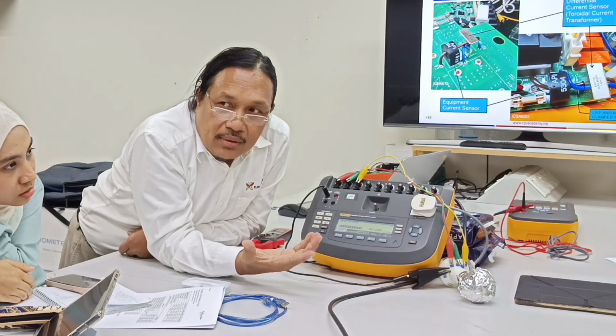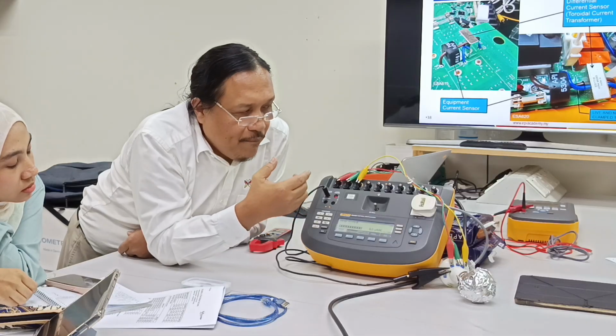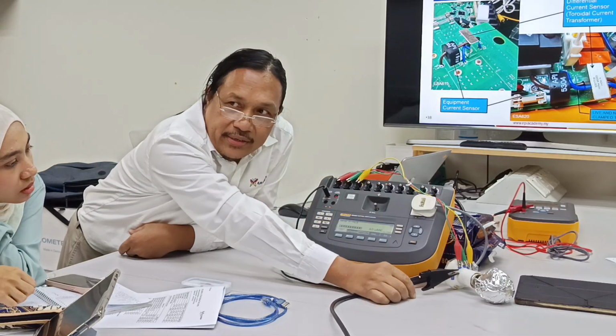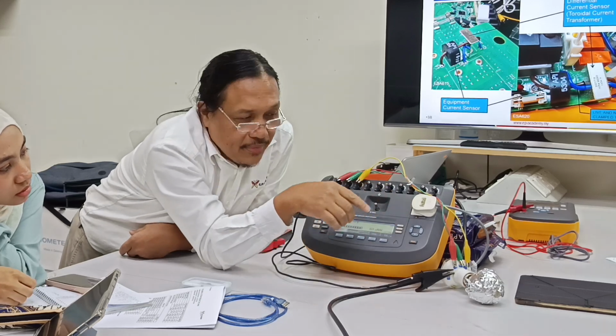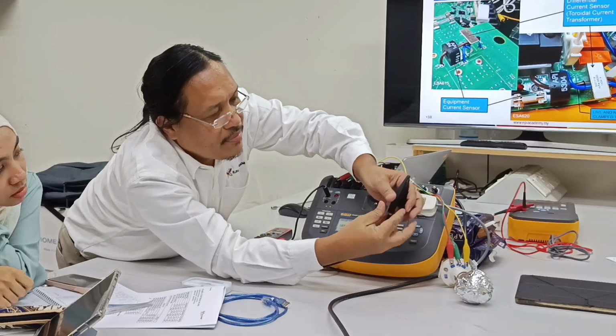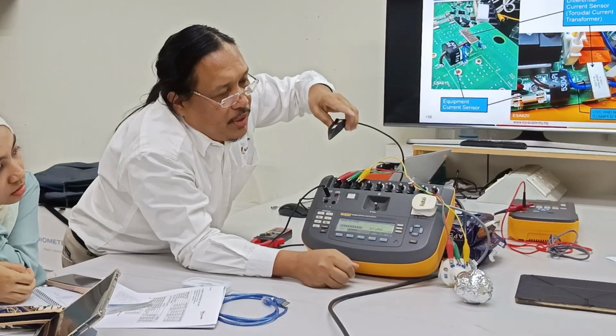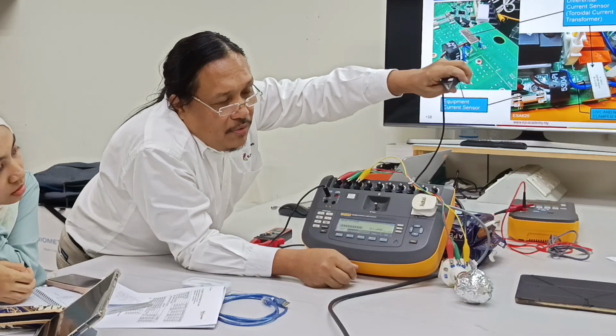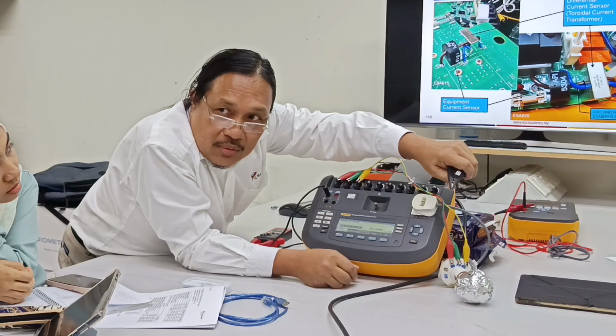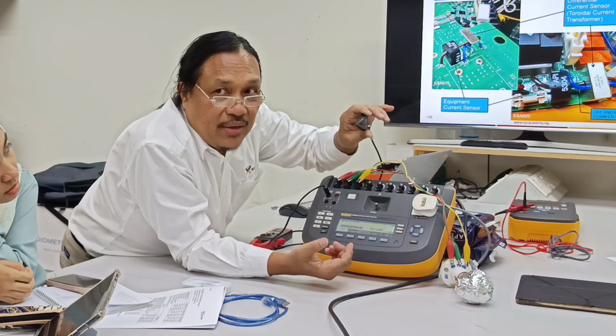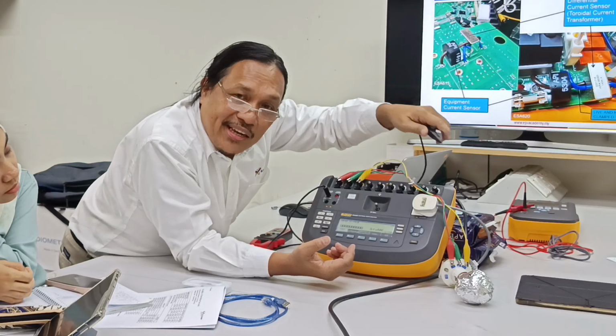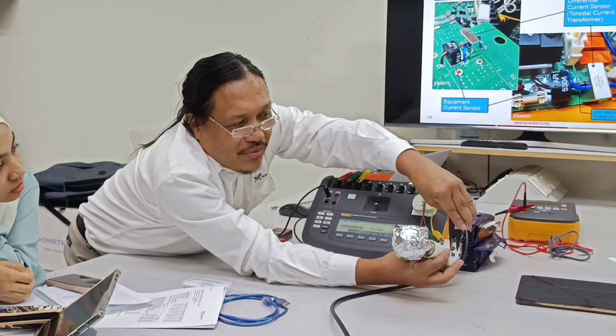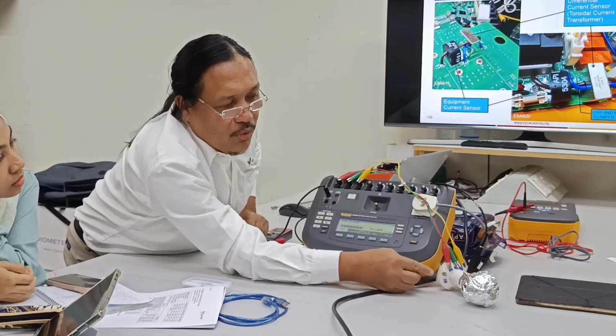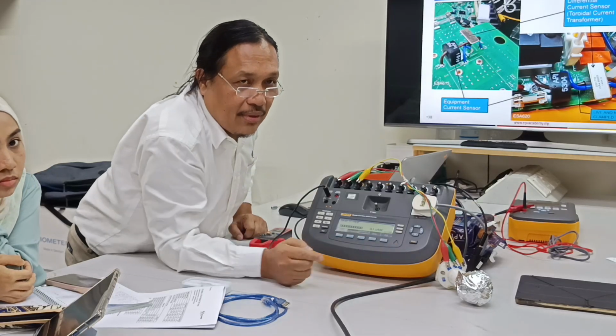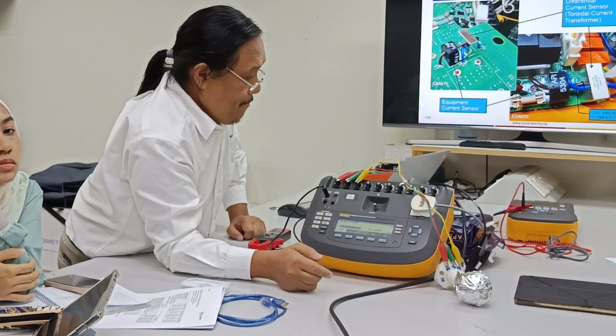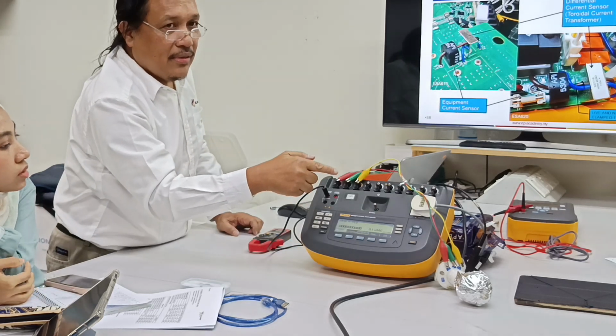How is the connection? We are talking about connection. Connect the applied part. Connect the non-earth. The ground is already connected here. But normally we do it like this. It's a bit confusing because the clip is now used for measuring earth leakage also. Unlike in 60601, where you don't need the clip to measure earth leakage, now you need the clip to measure earth leakage. So we connect this to the test point of the ground. So what happened to the non-earth? Earlier you put the non-earth, and now it is ground.